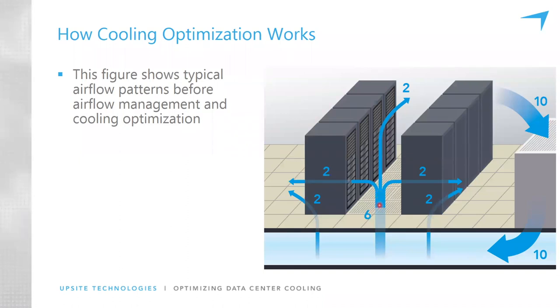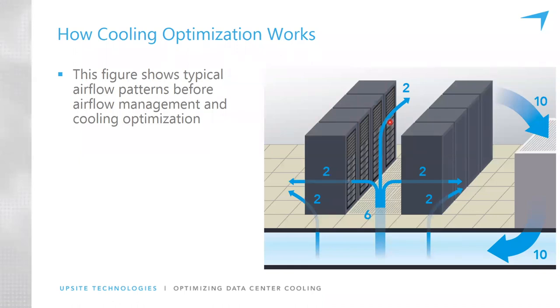Looking at the IT equipment in those cabinets, each row requires two units of air, for a total of four units of conditioned air required by the IT equipment. Here's a statement you don't hear very often: the amount of air moving through the IT equipment is completely independent of the amount of air moving through the cooling units or through the room. You could turn off all the cooling units and there would still be four units of air moving through all the IT equipment — they have their own fans and those flow rates are independent.